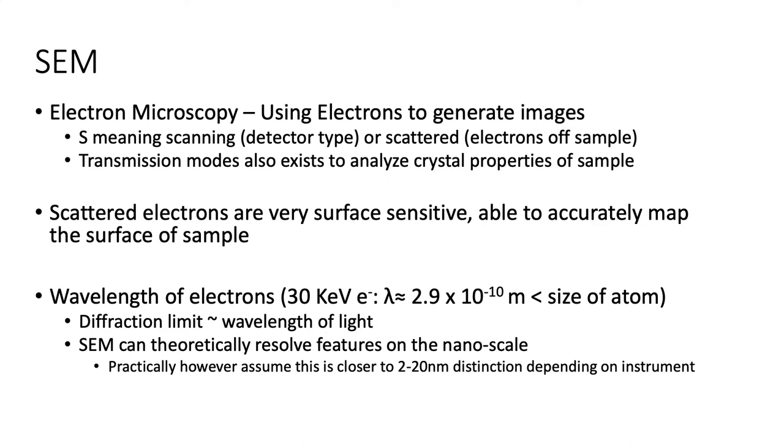The change in resolving power is what separates electron microscopy and optical microscopy. A term you may have come across is diffraction-limited microscopy. This is a known issue when trying to probe the nanoregime because light is strongly scattered when its wavelength is on the same order of magnitude as the sample. As visible light is in the 400 to 700 nanometer range, it cannot resolve features smaller than this. Electrons, however, have a wavelength roughly that of an angstrom, depending on the accelerating voltage, and can provide much higher resolution.